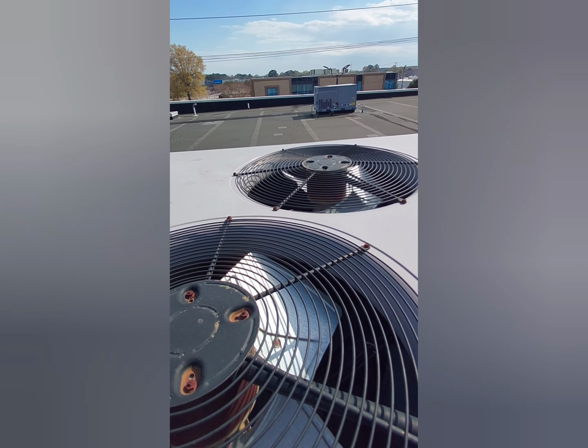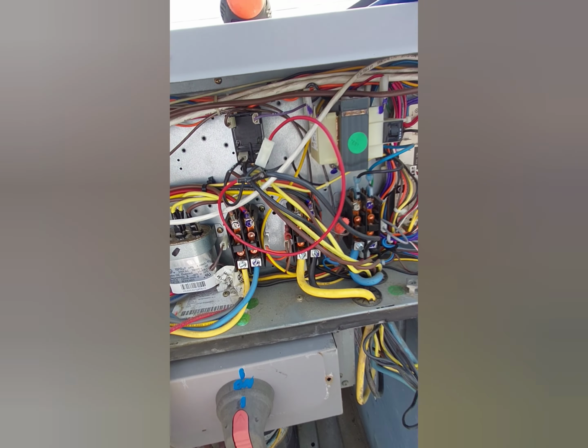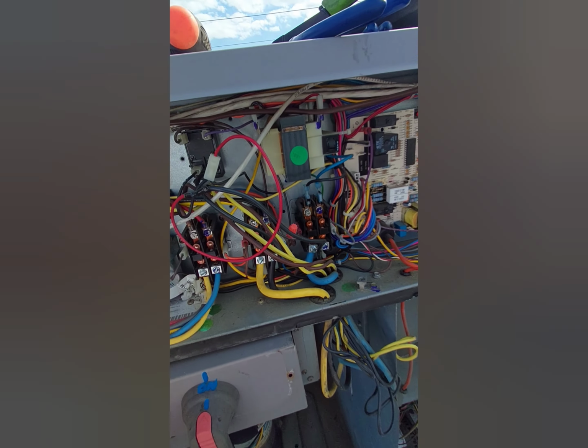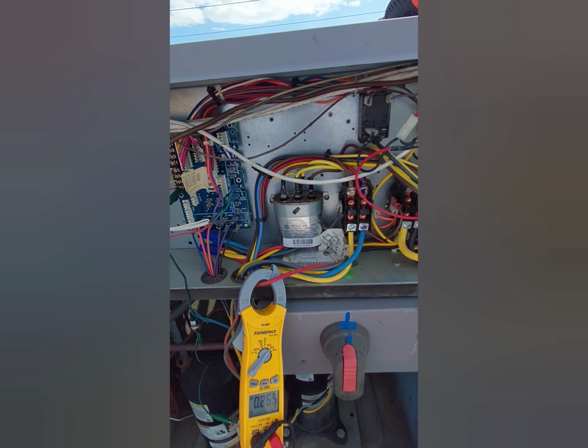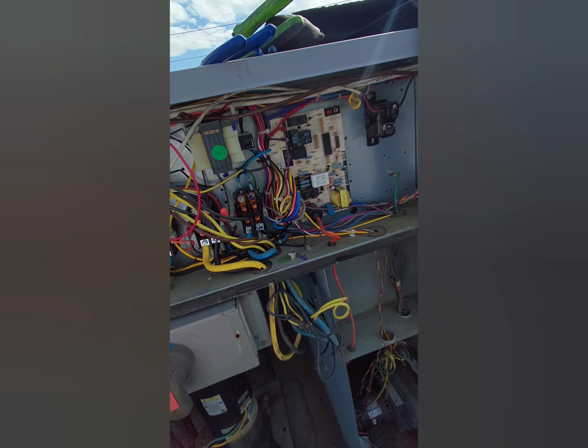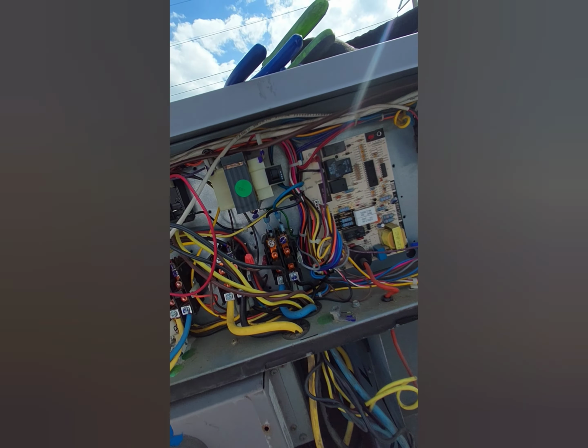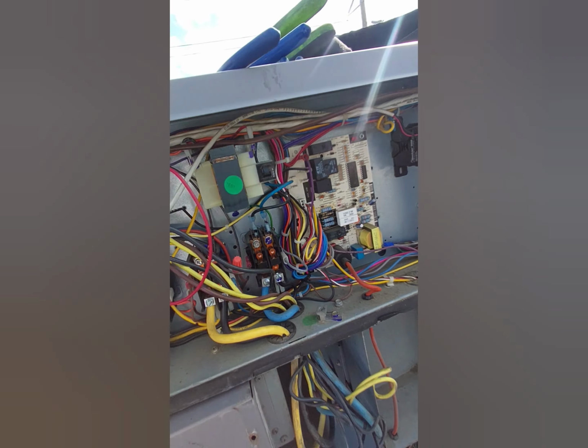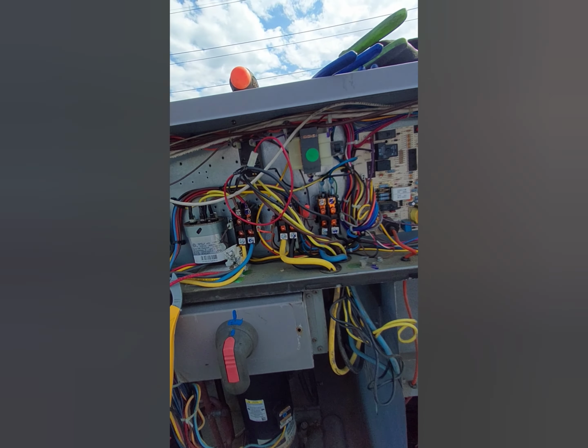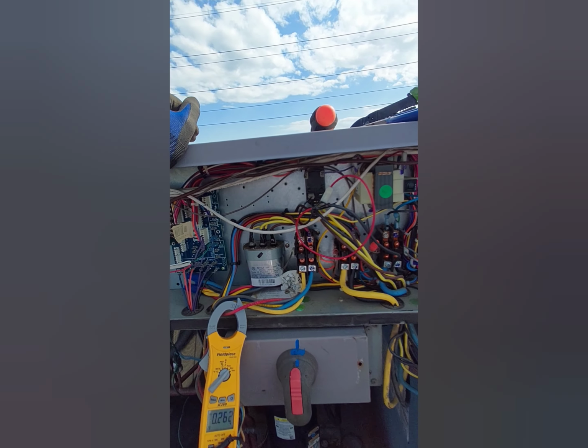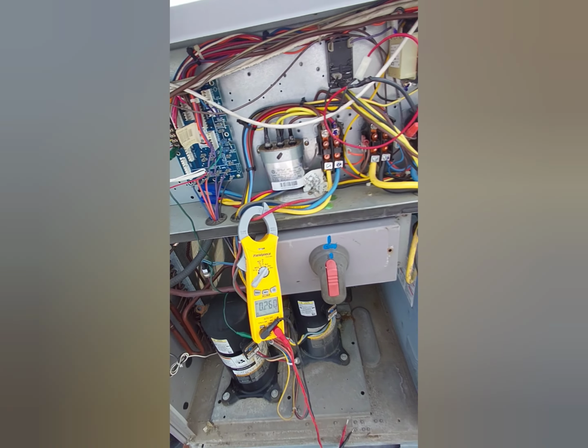Back fan works. So we got something in the circuit that's not allowing 24 volts to come through, and I gotta find that. If I had a tripod or something I'd set y'all up and find it, but I'm pressed for time right now. I got the disconnect in within the time I wanted, but now we gotta find out why this stuff isn't working.